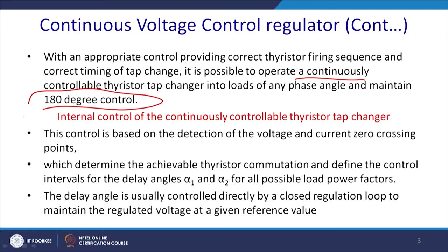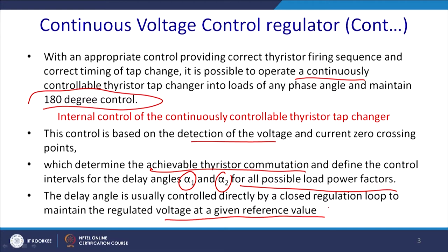The internal control of these continuously controlled thyristors will be discussed now. This control is based on detection of the voltage and the zero crossing point of the current, because here the current will lead the voltage, which determines the achievable thyristor commutations and defines the control interval for the delay angles alpha 1 and alpha 2 for all possible load factors. The delay angle is usually controlled directly by a closed regulation loop to maintain the regulated voltage at a reference value. So, this is the way it is controlled.